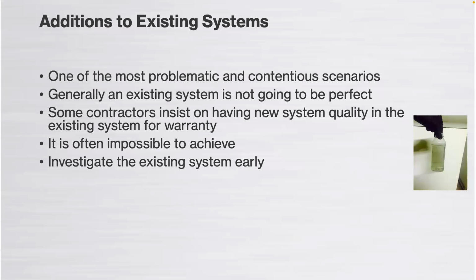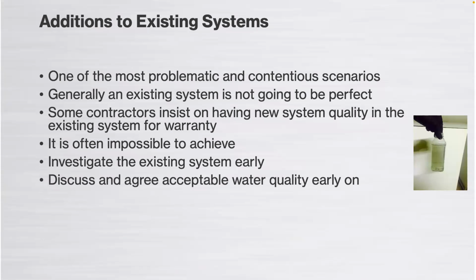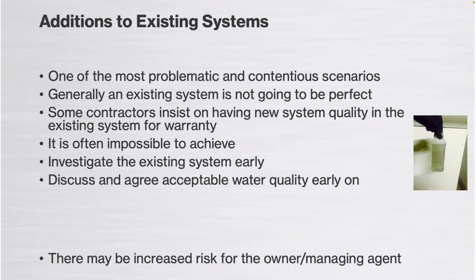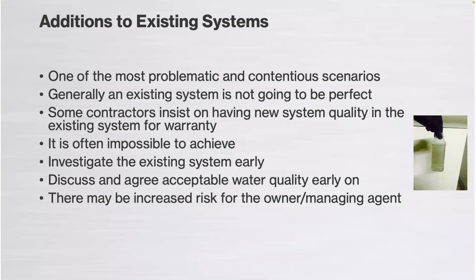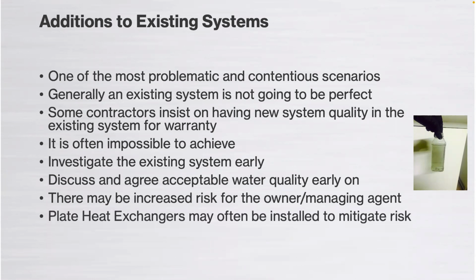So investigate the existing systems early, and discuss and agree acceptable water quality early on. Our solution, typically, we tell clients, if you've got old systems and you're adding new plant, to be honest, is putting our products on three months before, using that existing equipment, boilers, pumps, almost sacrificially, to clean up that system well before you look to add anything new. Basically make a head start, because there may be increased risk for the owner or the managing agent that they need to be aware of.